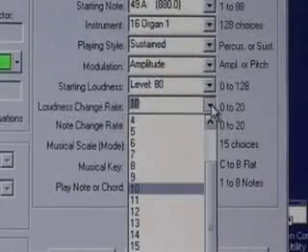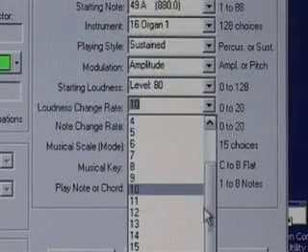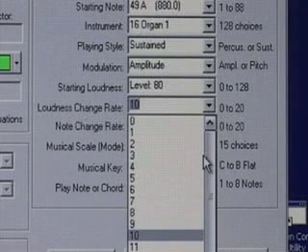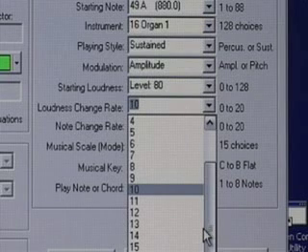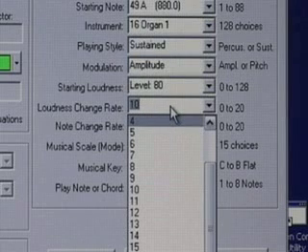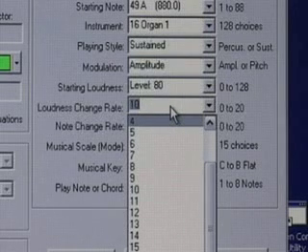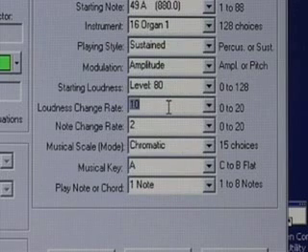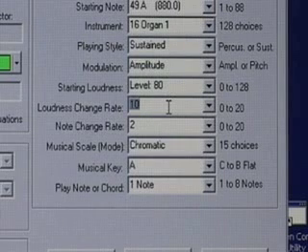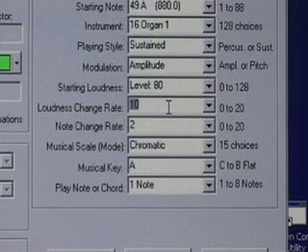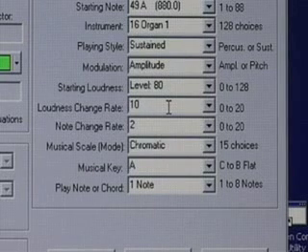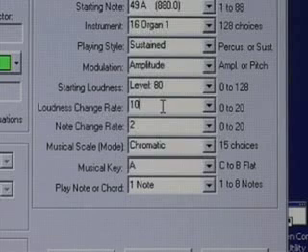We then pick the loudness change rate, which tells us how much the loudness will change as the condition is met to a greater or lesser degree. Zero means there's no change; 20 would mean a very large change. We're picking something in between: 10. What this basically means is that for every unit of the quantity — in this case microvolts — the loudness changes by a factor of 10. So if the level is exceeded by 10 microvolts, the loudness will go up by a factor of 10. Note that since we've said 'is less than' for down training, it gets louder as the signal gets lower.